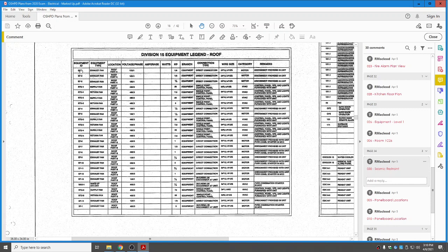Now let's go back up to the top of the chart, and we'll see the first one, EF1, equipment type. It's an exhaust fan. Its location is at the roof. Voltage and phase, the horsepower, the equipment branch, what type of connection to this exhaust fan. We have a direct connection, wire size, it's a motor, and a disconnect will be provided, it says, in the unit. Let's drop down to RTU number 1, return fan on the roof, 480 for the power, 3-phase. The wire size is shown here. Control panel with a VFD for variable frequency drive and lights furnished with unit. So this 3 number 12 and 1 number 12 ground is for the return fan at the roof.